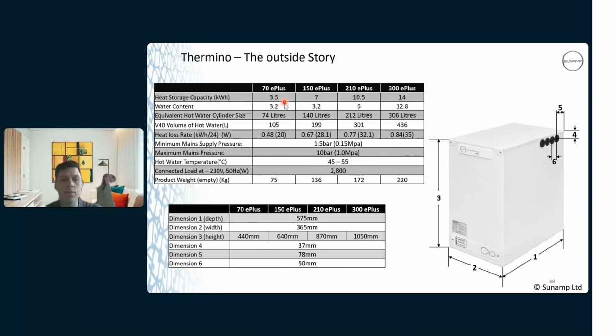So the V40, I've always quite liked this row. If you set a blending valve on our batteries, that's part of our mechanical components fitted to the plumbing, and you set that blending valve to 40 degrees on the outlet temperature, this is what you can achieve from the heat battery. So 70 litres is essentially up at 105 litres, and from our 300, you can actually get 436 litres. So when I was talking about the Guatemala project that we had, the interesting thing was that...